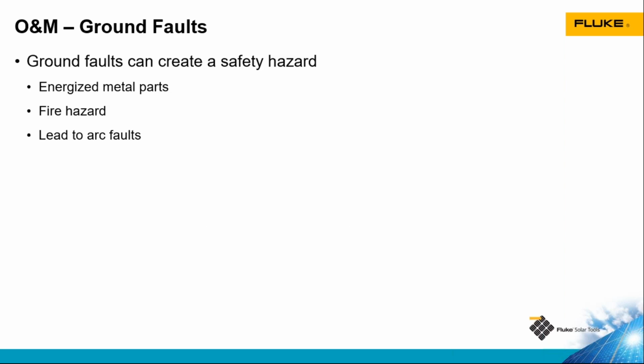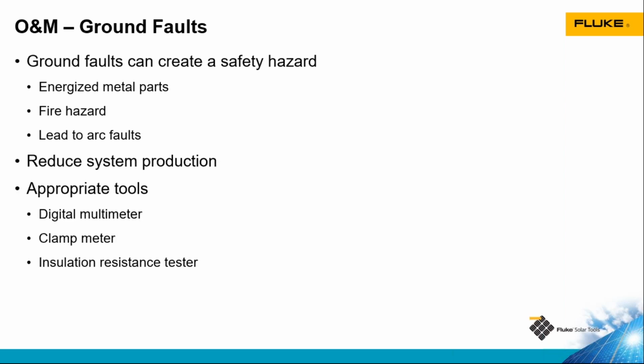Now, ground faults are a safety hazard. If there's current flowing to a metal part, that metal part may be energized, especially if it's not bonded and grounded well. Ground faults often arc. Arcing creates sparks, and sparks can create fires. We've seen ground faults create fires on both rooftop systems and ground-mounted systems, catching the grass on fire. If I'm losing current to ground, that means the current's not going to my inverter, so I'm losing some energy there, which is reducing the financial benefit of the system.